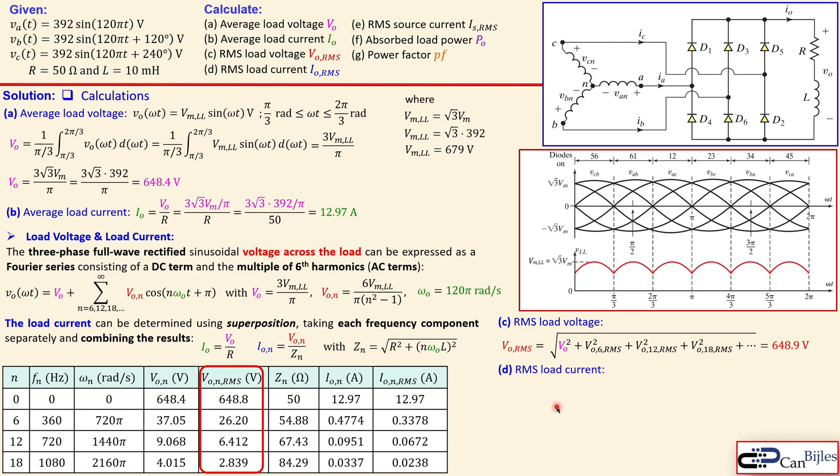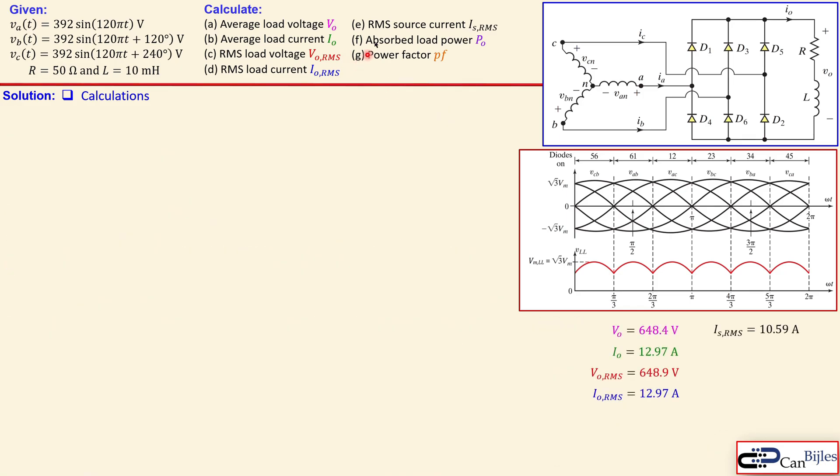The RMS load current can be then calculated using the column here so given in this part that is again using the similar formula average part the sixth harmonic 12th harmonic 18th harmonic so you add them up you actually get almost the exact same as this one so because these parts are not really contributing that much so the result will be here 12.97. The RMS source current is again calculated using this formula we have seen it also in the previous example and that will give you 10.59 amps. Okay now we have now the most of the parts here so only part left is the absorbed power and the power factor.